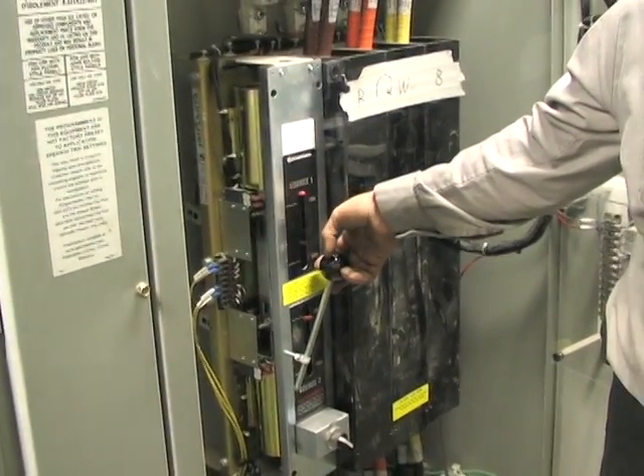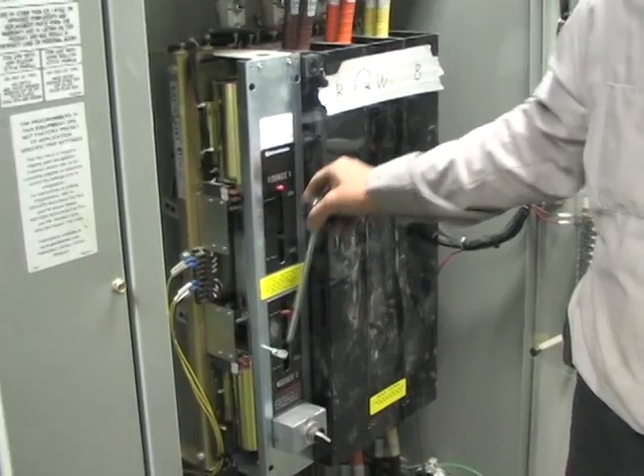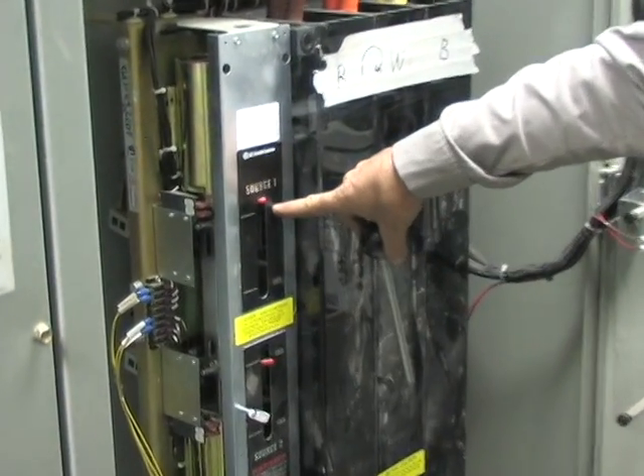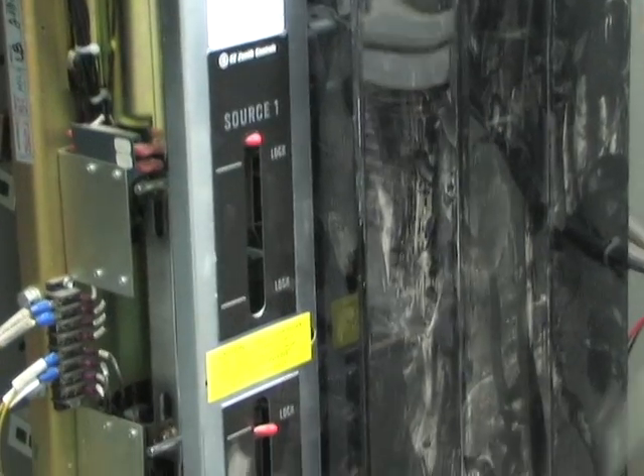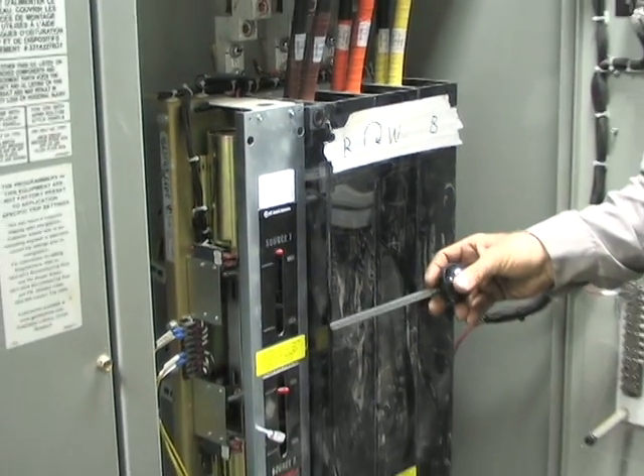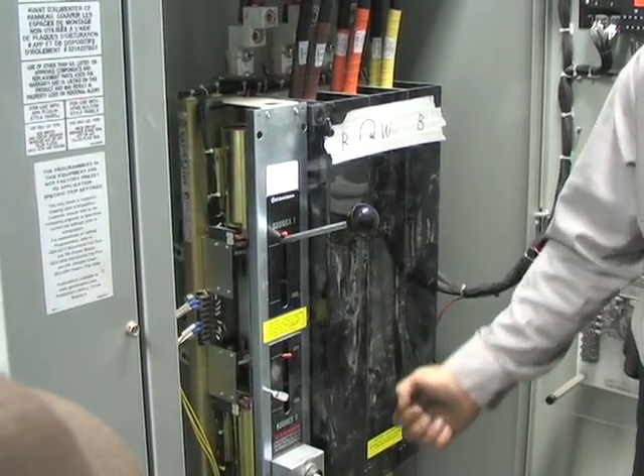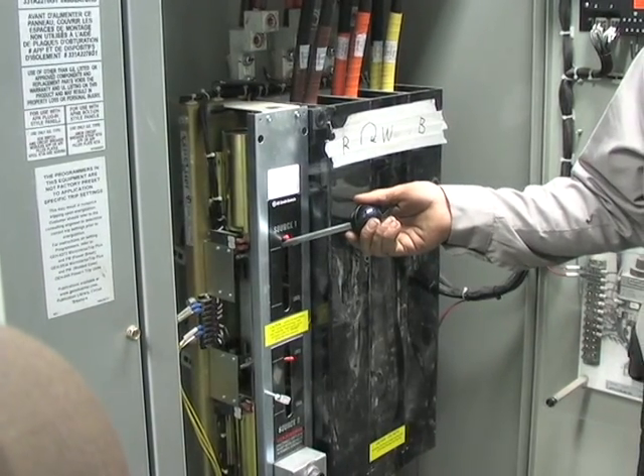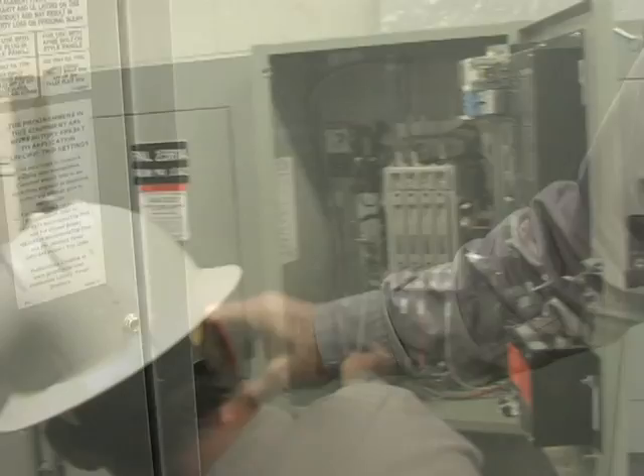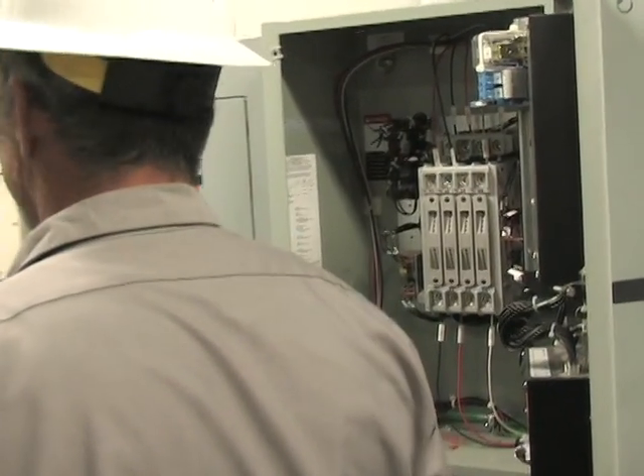Don't reach in here without gloves and safety gear. This is the manual switch rod — it engages in this hole or in this hole. Unlock one, unlock the second one. Everyone come through one at a time. So that's where this goes — in here, or in here. Push it in, push it down to the source you're looking for. Make sure the power is off. It's marked 'Normal' and 'Emergency.' Make sure the power is clear before switching.